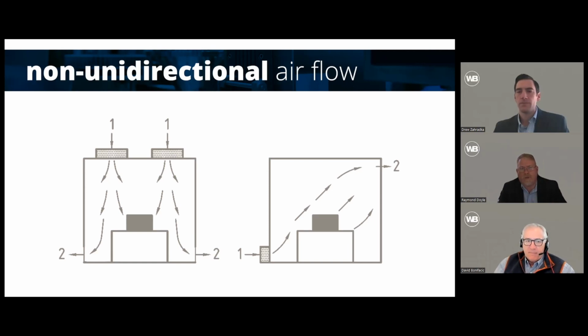Yeah, the maintenance and changing of the filters is a real important aspect when it comes to downtime of the equipment. And we can talk a little bit more in the operation, but the main point there is understand how dirty your space is. There's clean rooms that are very clean based on what's done in the space, and then there's clean rooms that have dirty activities. I'll use tablets or pellets or equipment. If you're making pharmaceutical tablets, it's a dusty process, and it still needs to be done in a clean room environment. So sometimes that exhaust can go back to the air handling units and have a lot of dust in it. And even when you recirculate it, you may need to have pre-filters on that exhaust to protect the ductwork. So there's a lot of different applications. To answer that question, we might want to get together with that person individually and make sure we understand the application. We could better answer that question. Okay, thanks.